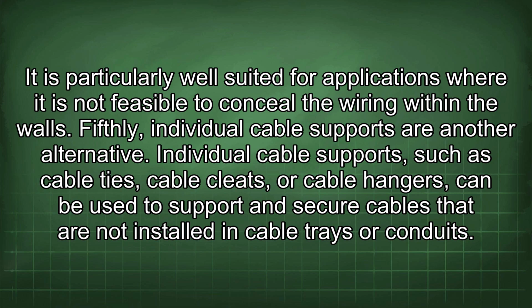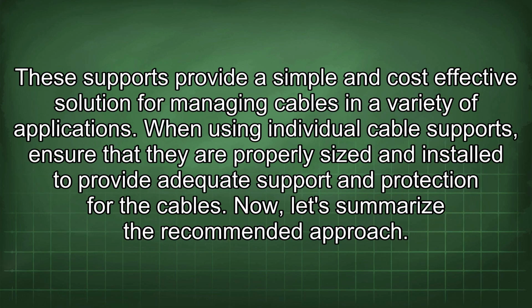Fifthly, individual cable supports are another alternative. Individual cable supports, such as cable ties, cable cleats, or cable hangers, can be used to support and secure cables that are not installed in cable trays or conduits. These supports provide a simple and cost-effective solution for managing cables in a variety of applications. When using individual cable supports, ensure that they are properly sized and installed to provide adequate support and protection for the cables. Now, let's summarize the recommended approach.